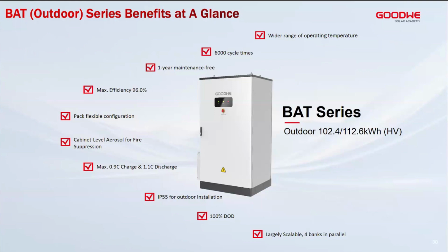So for the BAT series outdoor, we have 2 variants, the 102.4 and the 112.6 kilowatt hour. The same battery BAT still holds the same most similar features, just a bit tweaked here and there. So wide range of operating temperature, 6,000 cycles, 1 year maintenance free, efficiency 96%, pack flexible configuration because you can either choose the 102 or the 112 cabinet level.